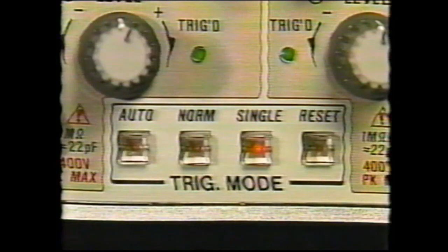In the automatic position, automatic sweep is selected. In automatic, there will be a trace on the display without an adequate trigger. It is used when initially setting the controls and when viewing DC or very low-level signals. In the normal position, the sweep remains at rest until the selected trigger source crosses the threshold level set by the level control. In the normal position, there will be no trace unless an adequate trigger signal is present.